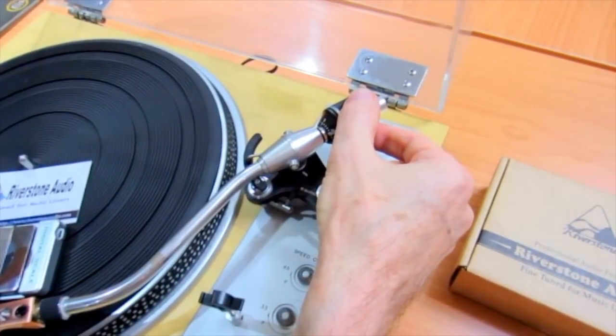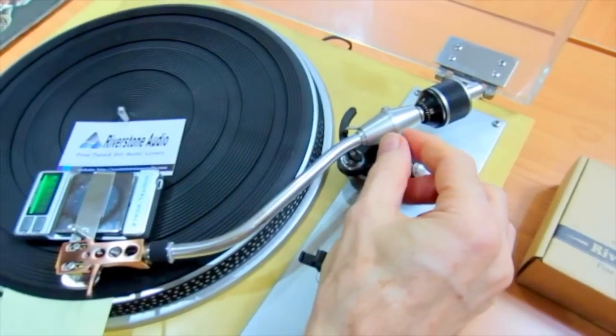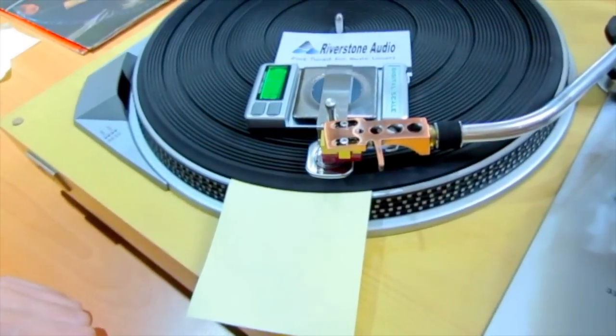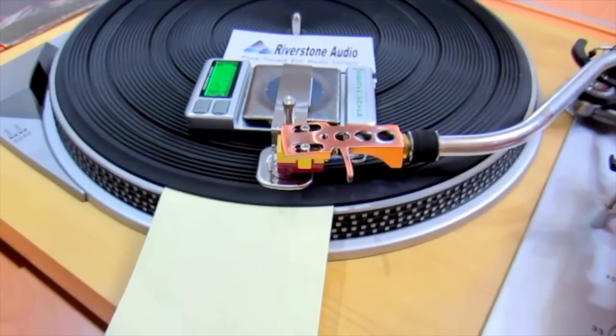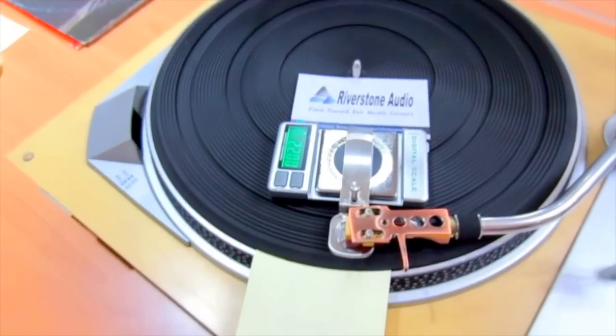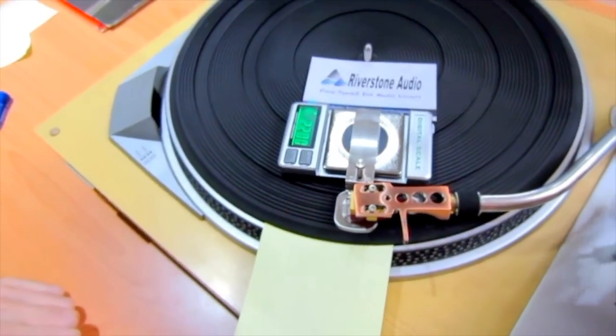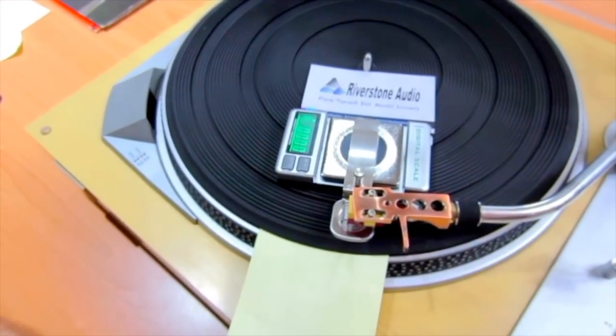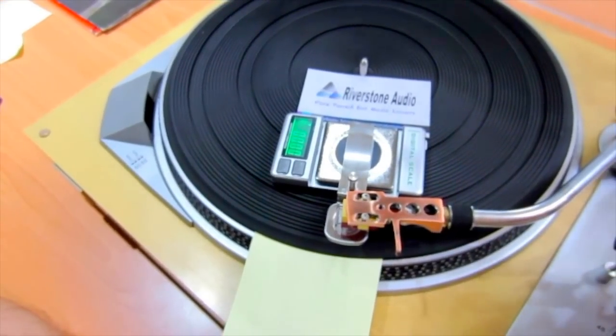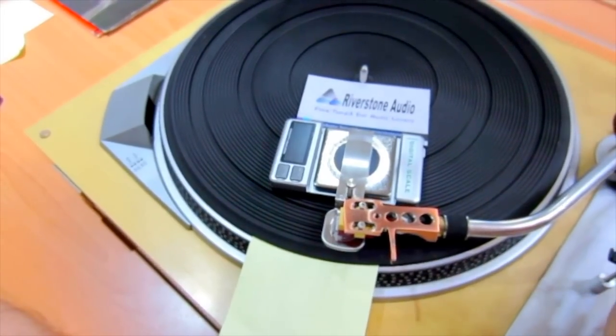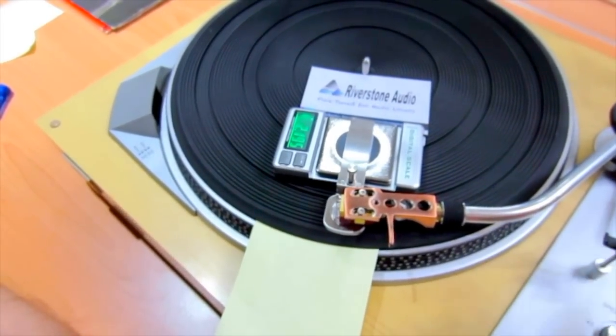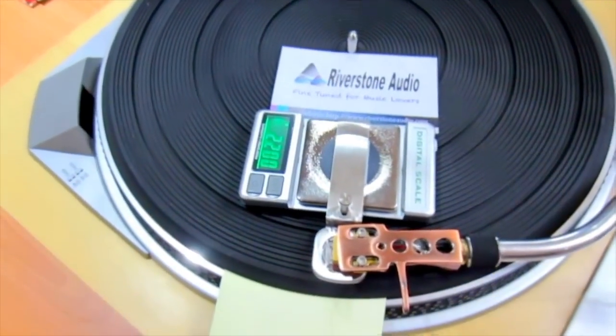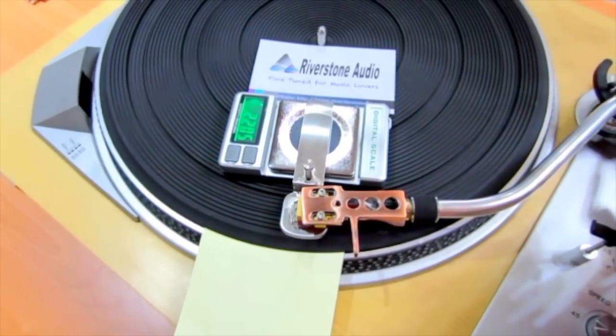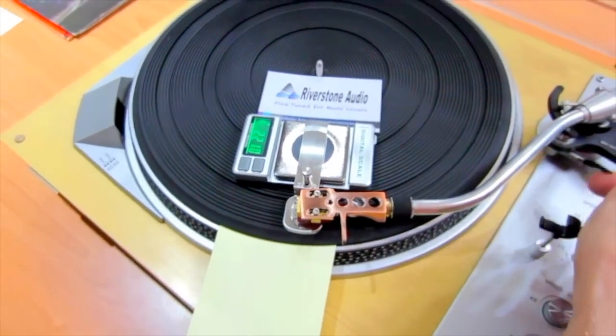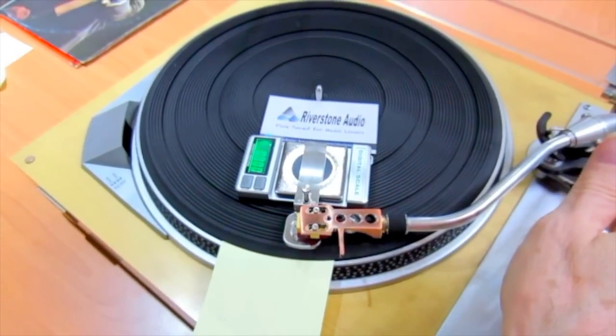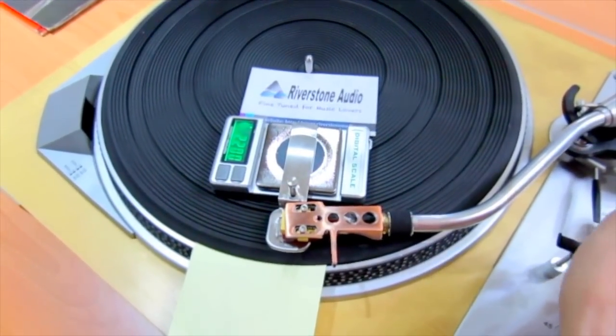counterweight, and let me add just a little bit of mass. Bring it back down. 2.205, 2.2. Again, make sure you're not breathing on the scale. So you may want to take a few repeat measurements. There's also what's referred to as slip-stick friction if you studied friction and wear in the past. So you can also get slightly different readings depending upon the quality of the bearings or the age of the bearings. Well, this one looks pretty consistent. This Victor turntable has been well maintained, although it's decades old now. All right, and let me take a third. You can just take the average of those. Okay, so I feel quite happy about this one.